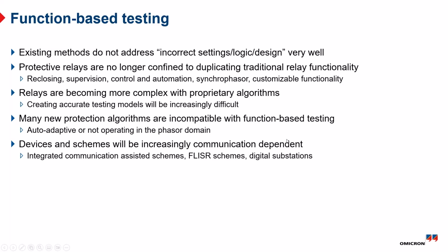Another big change that's happening: when digital relays first came out, they had to more or less copy the functionality of the previous electromechanical relay. So when you had a 51 element in a digital relay from 20 years ago, that function really had to operate like an old CO or an IAC electromechanical relay. And I remember when I was at Beckwith, we actually digitized the CO operating curve, humps, bumps, and discontinuities included, to make this digital relay act exactly like the electromechanical relay that it was replacing. Within the last 10 years or so, that has completely changed.